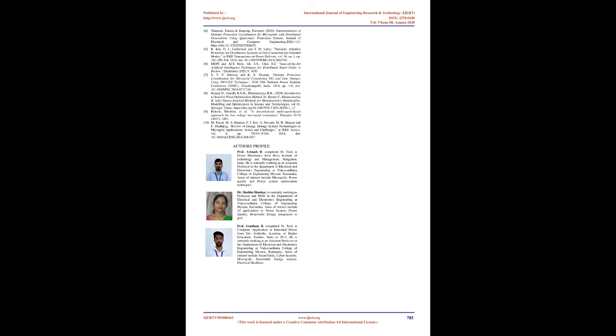Recalibrating the settings of each overcurrent relay is needed for each network emergency, viz., line outage, coupling or decoupling of DG, and swap between microgrid operation from grid-connected mode to island mode. Thus, a model that takes into account all operating emergencies, suitable for N-1 contingencies, plays a key role in overcurrent relay coordination. In the meta-heuristic approach, a single set of overcurrent relay settings, good enough to keep the overcurrent relays operational for all kinds of network topologies, is explained using the invasive weed optimization, IWO, and linear integer programming, ILP, technique. In this hybrid optimizer method, the miscoordination problem is modeled using ILP and solved using the IWO technique. The results of this technique are promising and provide results faster with fewer generations.